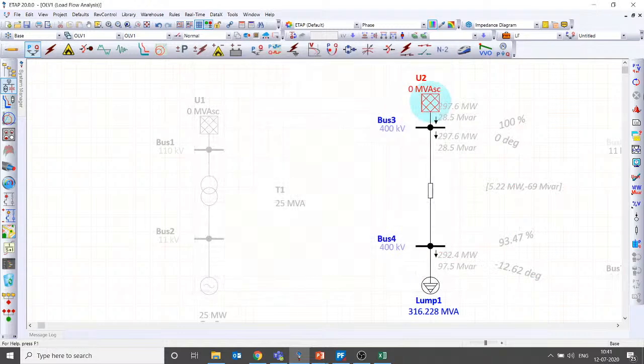That's what you need to look at, not the absolute values. That means when I have changed the angle of the swing bus from 0 degree to 30 degree, this bus angle becomes 17.38. But it is not really meaningful if we say 17.38 or 0 or minus 12.6. We need to always talk about the angle difference between this and this, that is del 1 minus del 2. Whenever you are talking about del, you have to talk about this relative angle only, not the absolute angle, because absolute angle will change when you change the angle of slack bus or swing bus.